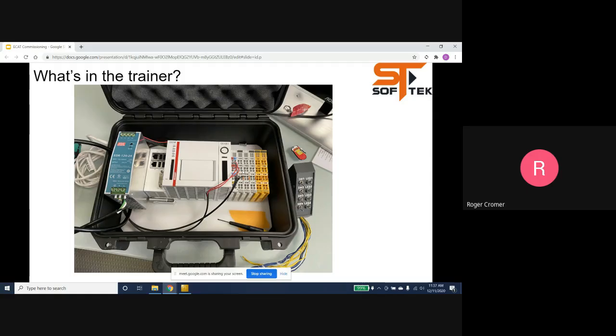They have to be unique. So you've got 2, 4, 6, 8, 10, 12, or 2, 4, 8, 16, 32, 64, 128, 256. The top row goes further. On your inputs, you're always going to have more inputs than outputs on a safety system. The outputs generally only have one bank of dip switches, but the inputs have two. It's the same with each of the safety slices, they have to be unique, and it's the same with the EJ modules, the ones that plug into the PCBs.